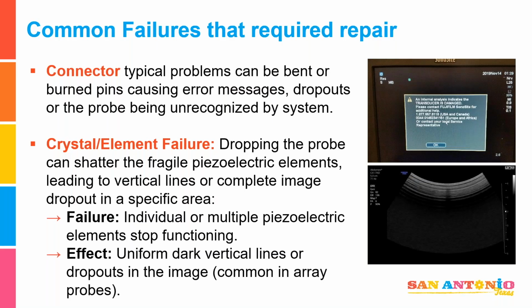Crystal element failure is fairly common, right? You drop a probe and now you have crystal failure. But it doesn't have to be crystal failure - it can look like the line on the left there. Right here is a dropout. Everybody says, well, that's a crystal problem. But that could be a cable problem too, or a problem with the ultrasound machine's transmit or receive board. You have to figure it out.